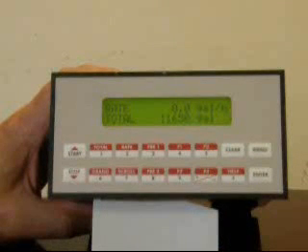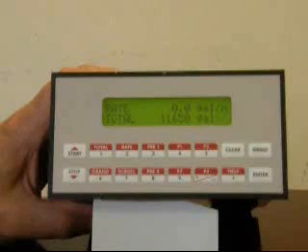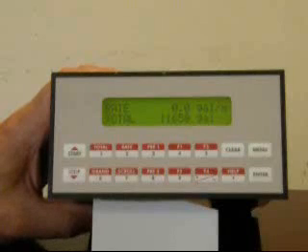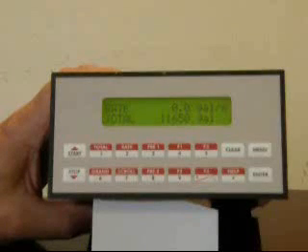That would normally complete the easy setup of the instrument, and the instrument would be ready for use. Now you may be aware that the instrument did not ask us about the type of sensor being used, its output signal to be expected, and so on. The easy setup is normally used when there's a voltage pulse being applied to the instrument from a flow meter. If you have other signal types, such as contact closure or magnetic pickup, additional setup would be required, and there you would need to use the actual setup menus of the instrument.